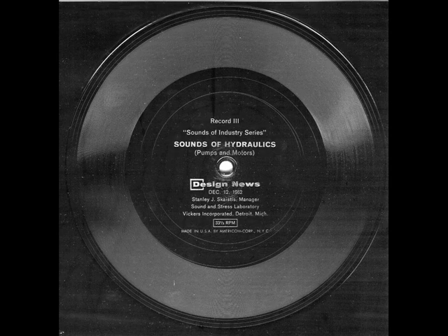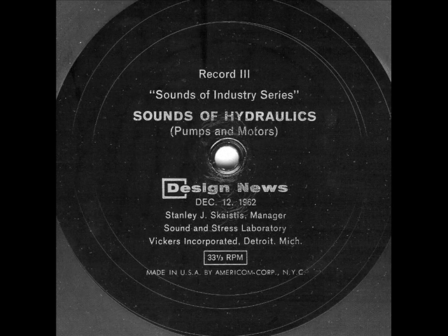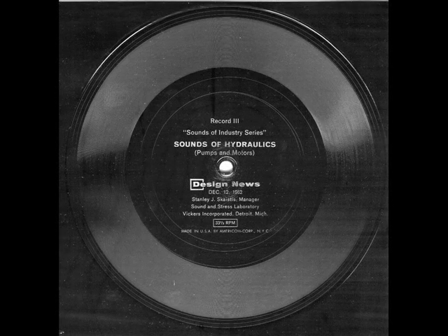In this article, we have shown how airborne noise in hydraulic systems can be controlled by proper choice of operating parameters. Although a discussion of liquid-borne and structure-borne noise is beyond the scope of this article, these effects are also reduced by the procedures demonstrated. Further reductions in noise can be achieved by avoiding resonance in the design of system components, by isolating structure-borne noise, by acoustical filtering of liquid-borne noise, and by the use of attenuating devices such as enclosures and barriers.